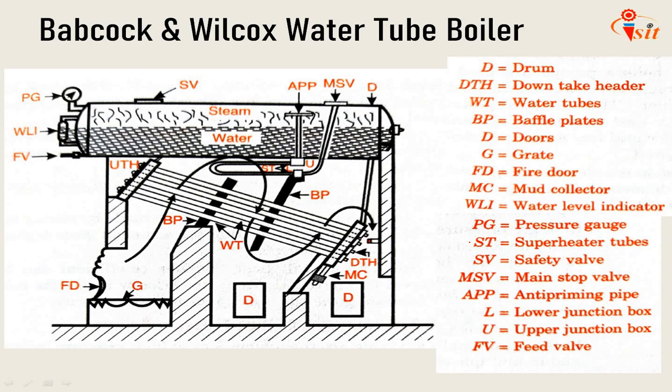The first type of water tube boiler, which is very famous and widely used, is the Babcock and Wilcox water tube boiler. Water tube boilers are used when pressure above 10 bar and capacity in excess of 7000 kg of steam per hour is required. The Babcock and Wilcox boiler is an example of a horizontal straight tube boiler and may be designed for stationary or marine purposes.